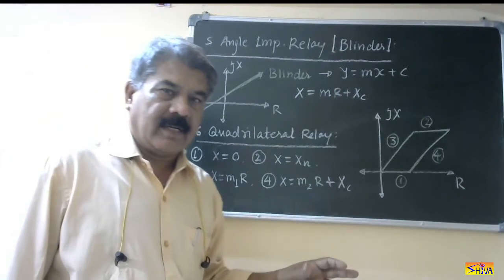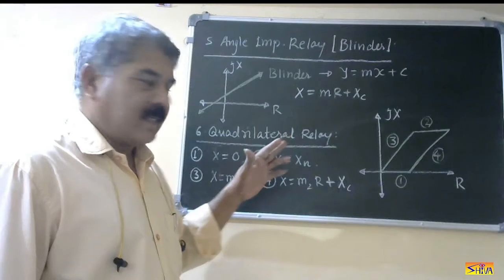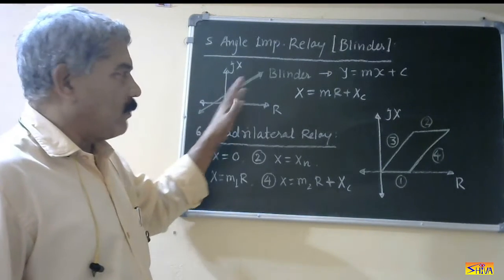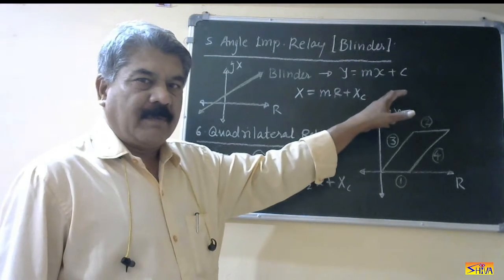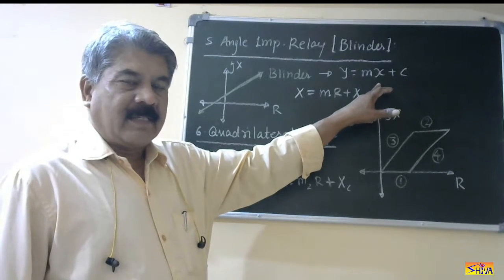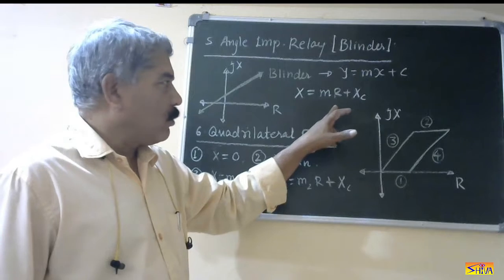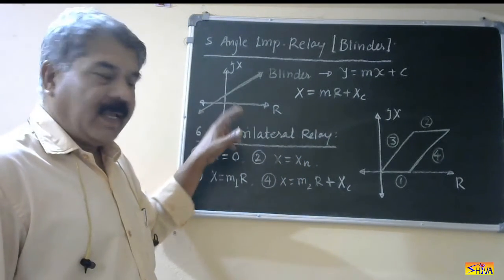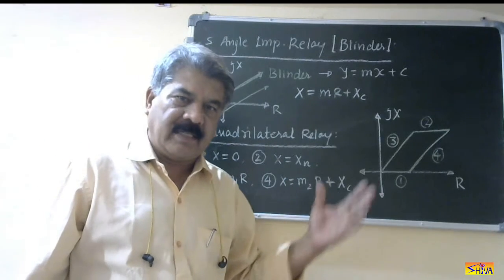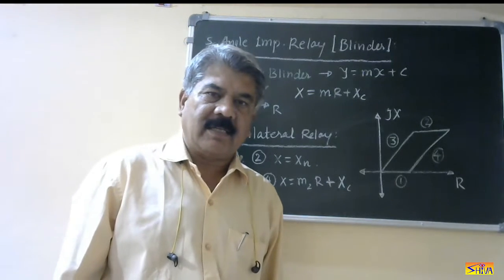The fifth type is the angle impedance relay, also called the blinder. The characteristic of the blinder or angle impedance relay is a straight line at some angle in the R-X diagram. In general, a straight line has the equation y = mx + c. In the R-X diagram, y represents reactance X and x represents resistance R. So the characteristic of the blinder is X = mR + Xc, where m is the slope and Xc is its intercept on the reactance axis. The line can be at any angle, so m and c can vary, but the characteristic is always a straight line — therefore it is called an angle impedance relay or blinder.